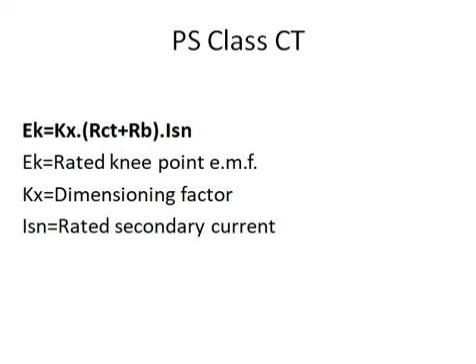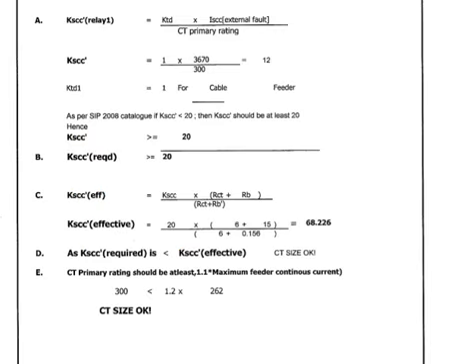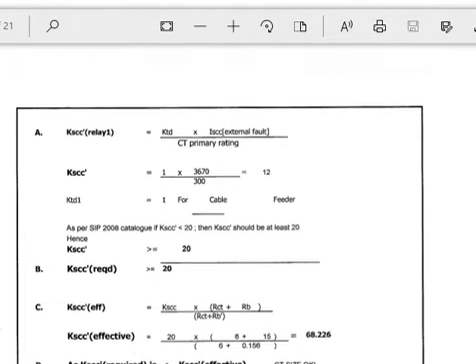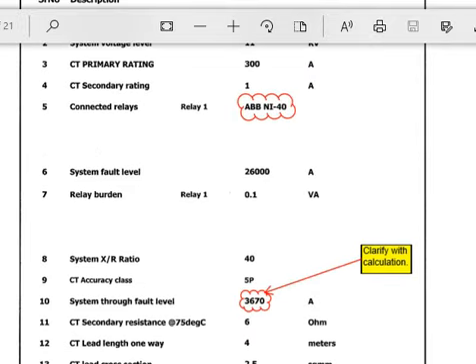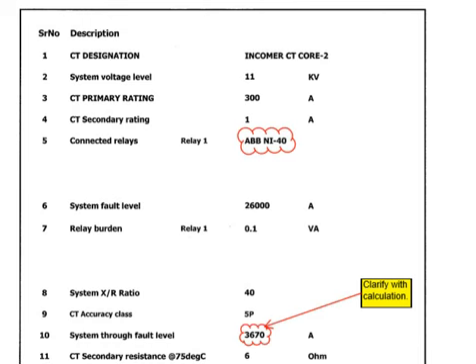Now let us look at a worked example of CT sizing. Suppose at an 11 kV voltage level, the CT ratio is 300/1 ampere — primary current 300 A and secondary current 1 A. The relay used is an ABB NI-40 relay with a relay burden of 0.1 VA. The CT accuracy class is 5P and the CT secondary resistance Rct is 6 ohms.